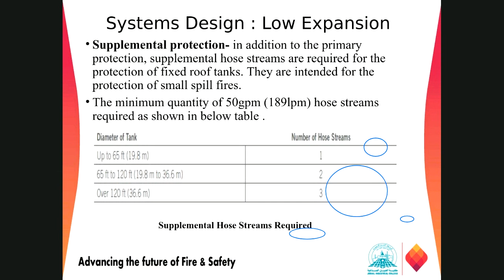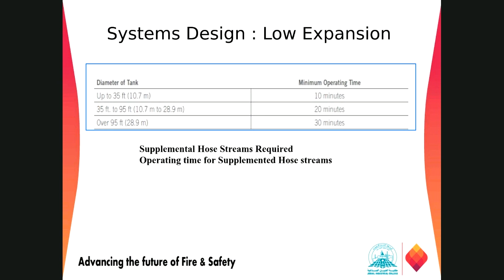Normally, when you are fighting fire, the fixed fire protection system is fighting the fire, and maybe we need a manual attack from the nozzle or the monitors, at least to fight the fire manually, right? The rate should be a minimum of 50 GPM for one hose stream, as per this table. And the time duration we need to supply is at least 10 minutes, 20 minutes, 30 minutes, based on the diameter of the tank. So everything regarding the foam system design is based on the diameter of the tank, types of fuel, their flammability range and flash point. We have to consider all those things before selecting the fire protection equipment.